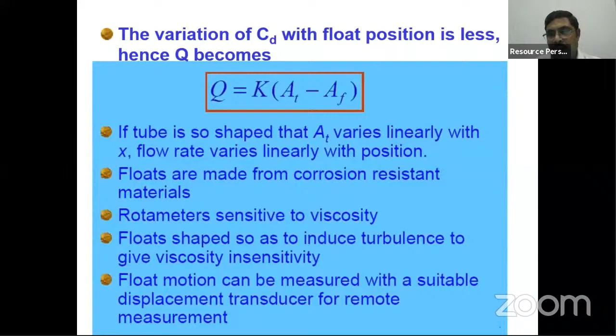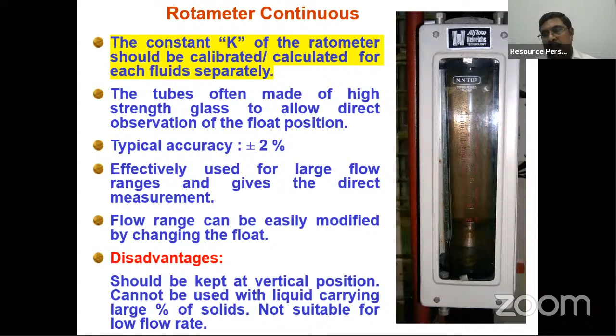And again, the rotameter is also used for very clear fluids. If there is any contamination in the fluid, you cannot use it. It's ideally suited for low density flow like water, and if the viscosity is too high, then of course you cannot use it. This is the photographic view. The best accuracy you will get is about 2%, provided you use the rotameter carefully. And the pipe diameter can be anywhere between ½ inch and maybe up to 10 inch.